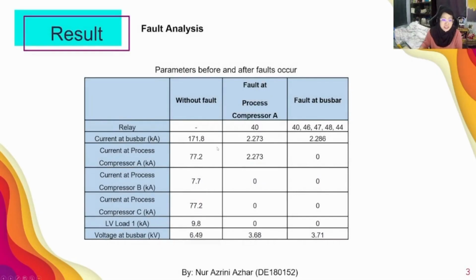For the last part, the parameters before and after faults occur. As you may see here, there are some differences. The current at the bus bar without fault is 171.8 kiloampere, while for the fault at process compressor A it is 2.273, and lastly for the fault at the bus bar, the current will be 2.286 kiloampere. So you may see it differs specifically.